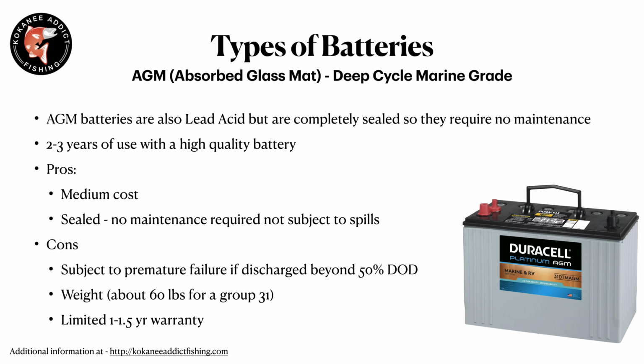The next type of battery is an AGM. It basically builds on top of the lead acid, and it's a sealed battery that requires no maintenance. Similar to the lead acid, you're going to get 2 to 3 years of use with a high quality battery. The cost is a little bit more on these, about double the cost of the ones that you have to maintain. One nice thing is they're sealed, so there's no topping off fluid.